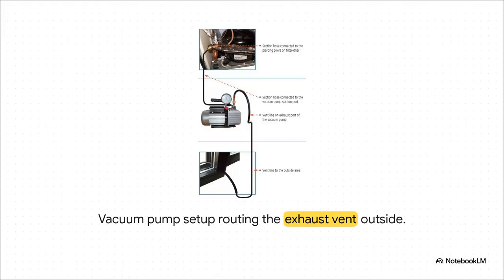When you're setting up your vacuum pump for flammable gases, routing is everything. The suction hose gets securely connected from the piercing pliers straight to the pump. But the crucial part is the exhaust vent line on the vacuum pump. It has to be safely routed all the way to an outside area. This guarantees that any residual flammable fumes pulled from the system are exhausted completely outdoors, rather than filling up an enclosed room where a single spark could set it off.